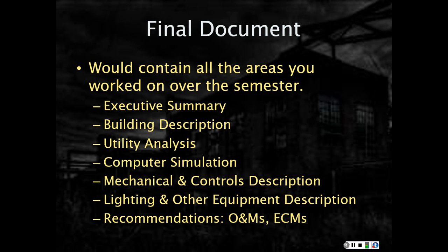Then you'd have the recommendation area, O&Ms first typically, and then ECMs or ECOs, in order of their simple payback, shortest to longest. Now remember, in the O&Ms and ECMs, they would be listed individually, calculated first, and then combined effects, typically separate, and noted as such.